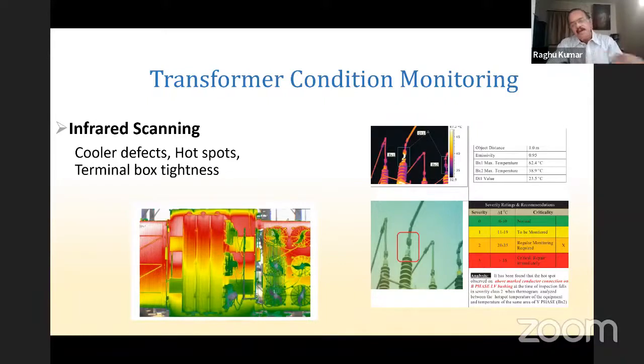Next comes the bushings. For the overhead bushings, what you see here, thermal scanning is done, and delta T, that is the temperature difference between the two bushings, is checked. If the temperature difference is within 10 degrees, it's considered normal. But if the temperature difference goes up to 20 degrees, then the monitoring is continued.